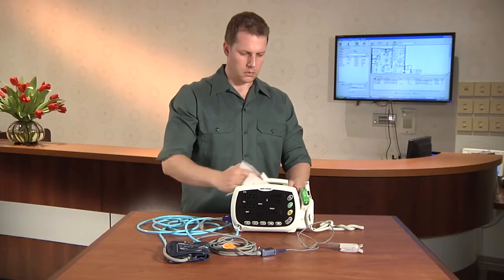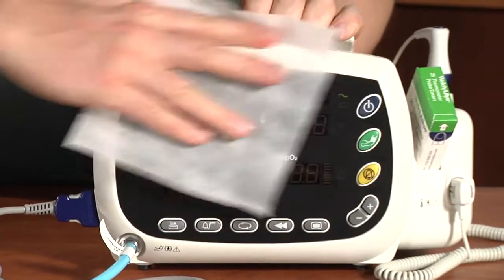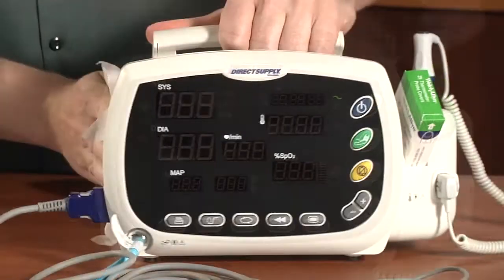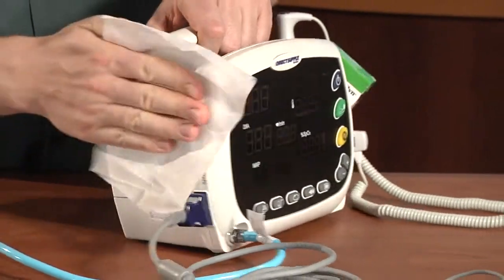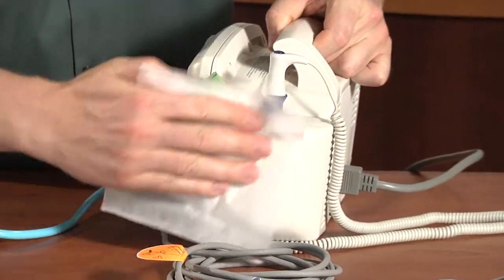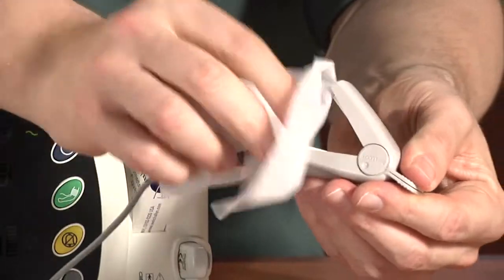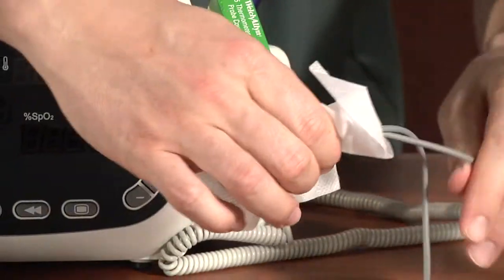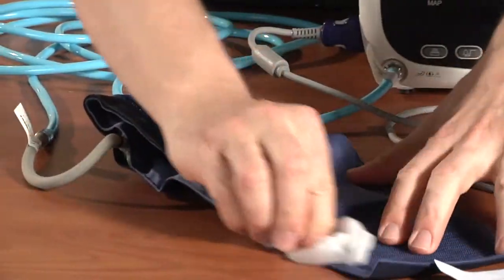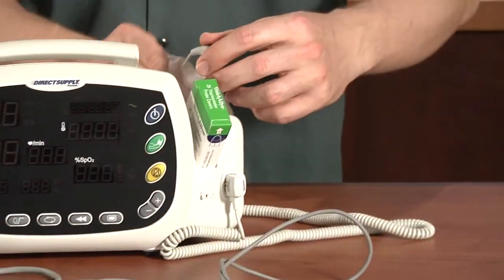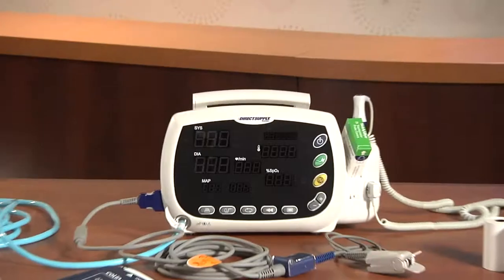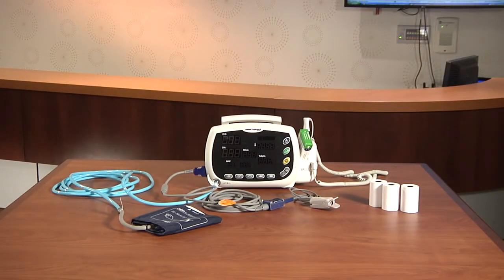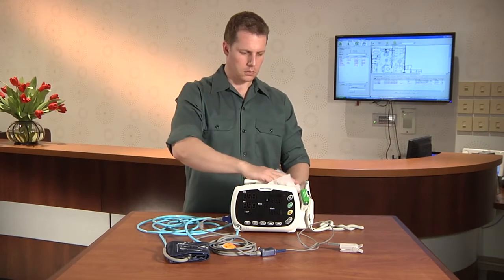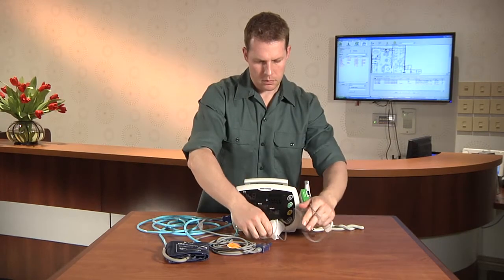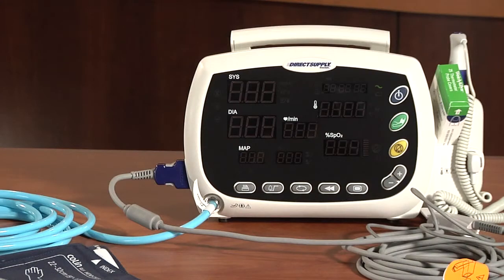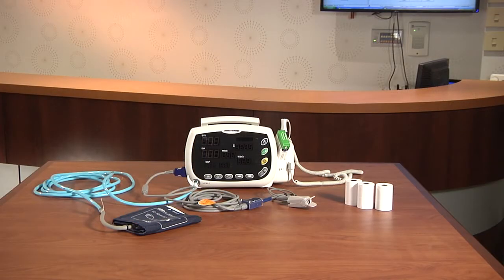For cleaning, be sure to always follow your community's cleaning procedures. The entire surface of the monitor may be cleaned using pre-moistened isopropyl alcohol wipes. Also, be sure to wipe all surfaces of the sensor and cable. Be sure to clean the monitor attachments, including the pulse oximetry sensor and cable, blood pressure cuff and cable, and temperature probe and cable. Never allow any liquids to enter any monitor connector. If a connector does come in contact with a liquid, clean and dry thoroughly before reuse. If you have concerns about monitor safety, do not use the monitor and contact Direct Supply.